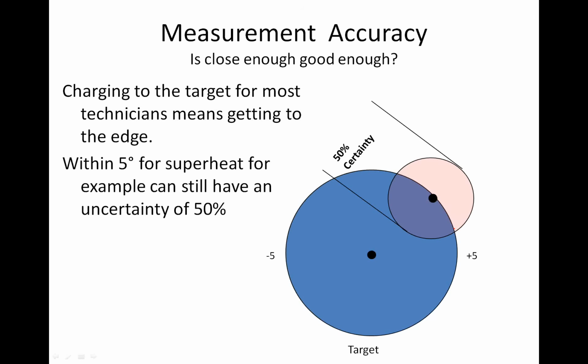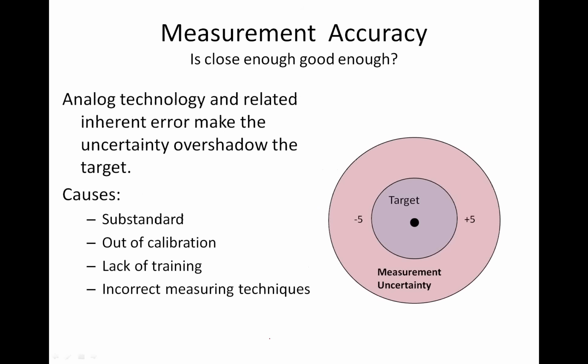Well, what he didn't consider is what's outside of this blue circle, which is the measurement uncertainty. There's still a 50% uncertainty that the technician didn't get the measurement right because he hasn't taken into account the measurement uncertainty. Yeah, he's within 5 degrees of the target, but how close is his measurement? And this is where, when we look at overall how accurate we got to be, if you don't take the uncertainty into account, you're going to get yourself in trouble. Analog technology and a related inherent error make the uncertainty overshadow the target. In other words, you say plus or minus 5 degrees, and if it called for 15 degrees and you were exactly at 15 degrees, there's still so much uncertainty in your measurement that you really probably aren't where you think you are.